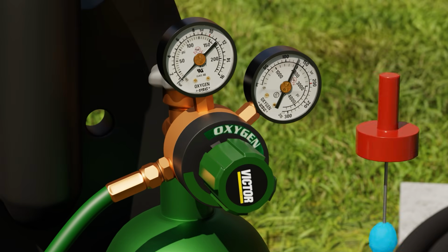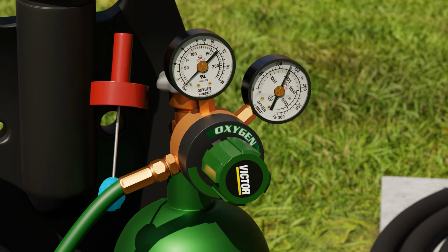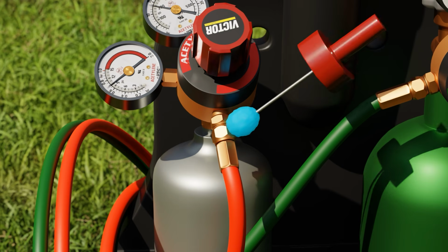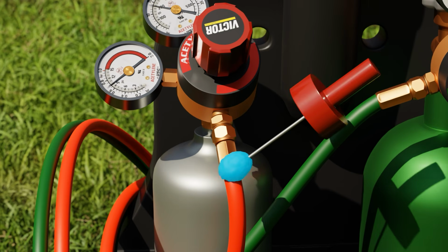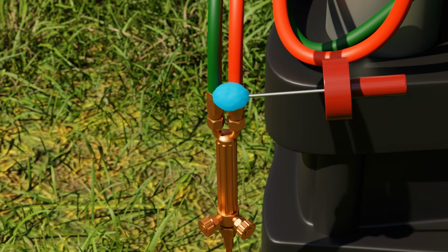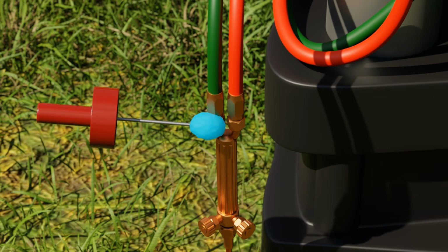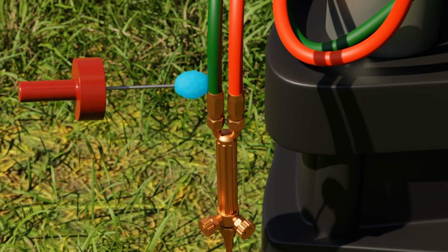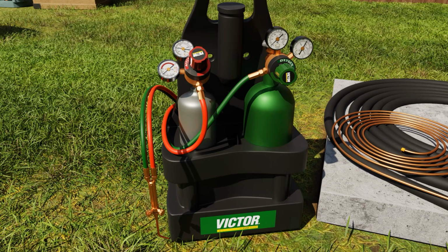Next, turn your regulators in, or clockwise, so that you have a bit of outlet pressure, then test for bubbles on the outlet side. As a general rule, when you're setting up the outlet pressure on your torch regulators, you need to do this with the torch handles open, meaning with the gas flowing.